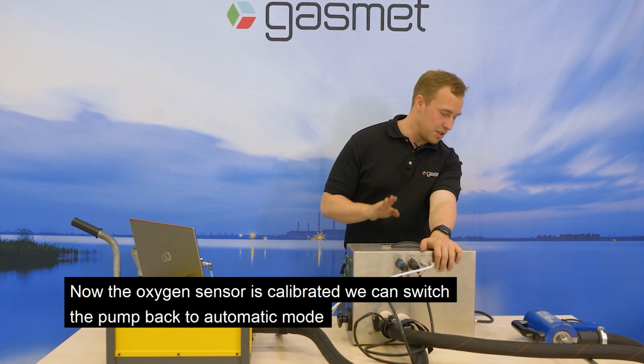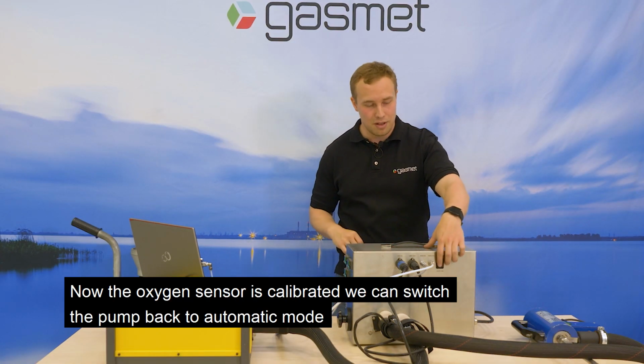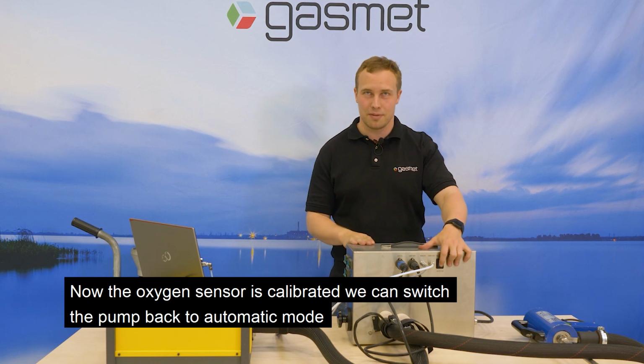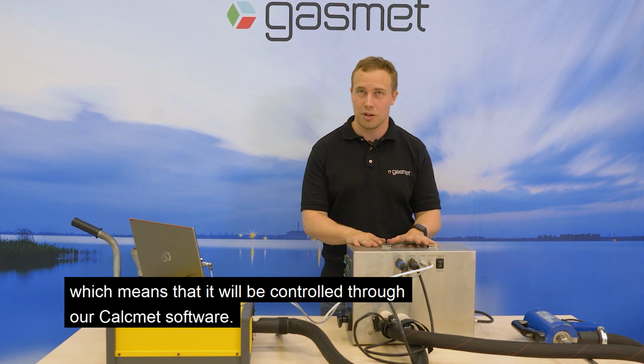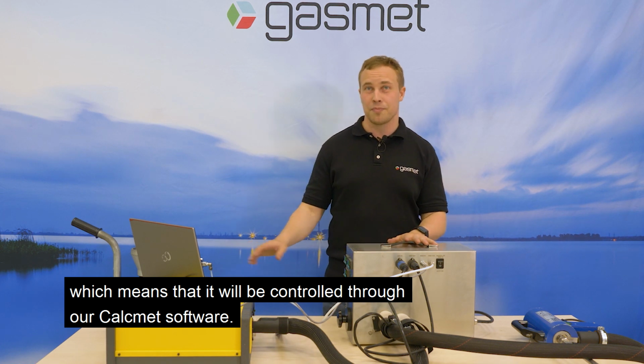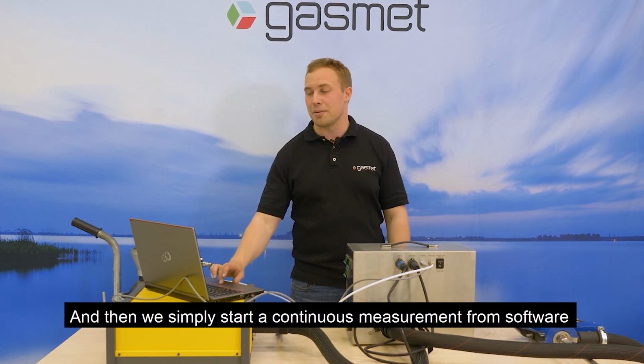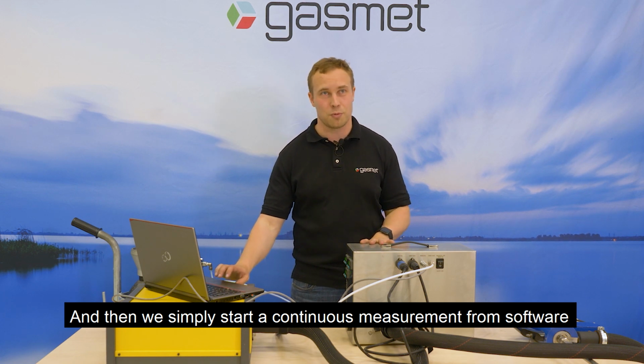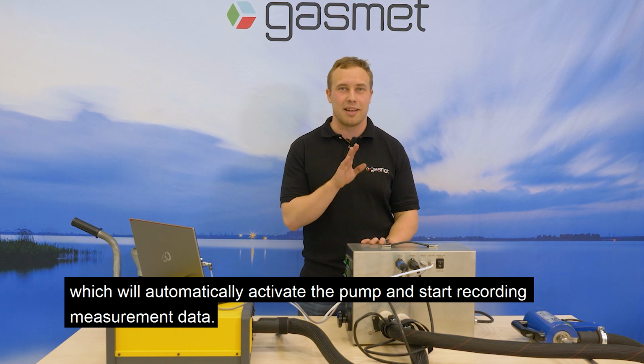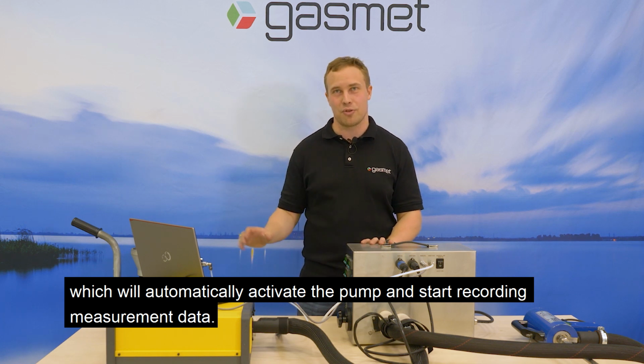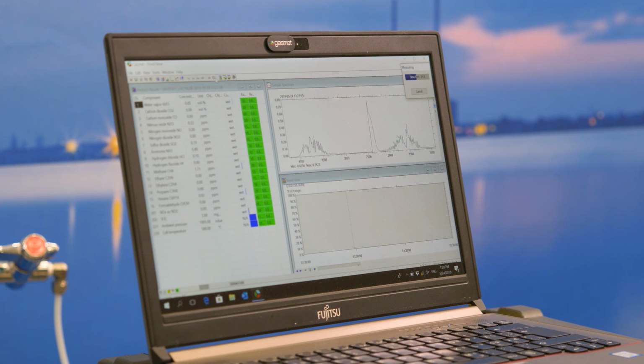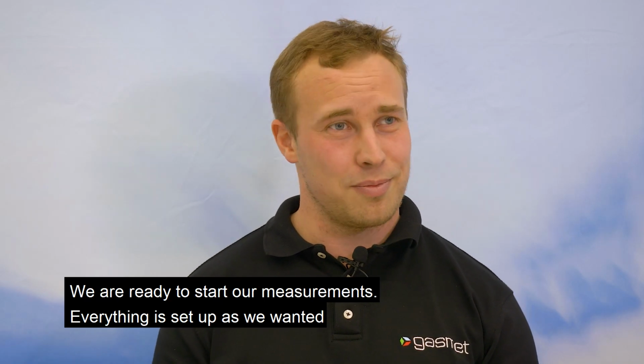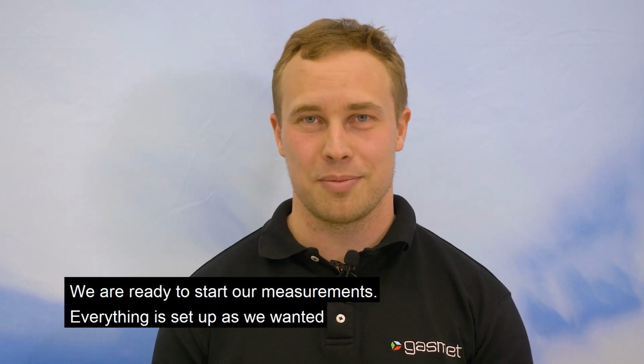Now the oxygen sensor is calibrated, we can switch the pump back to automatic mode, which means that it will be controlled through our Calcmet software. And then we simply start a continuous measurement from software, which will automatically activate the pump and start recording measurement data. We are ready to start our measurements. Everything is set up as we want it.